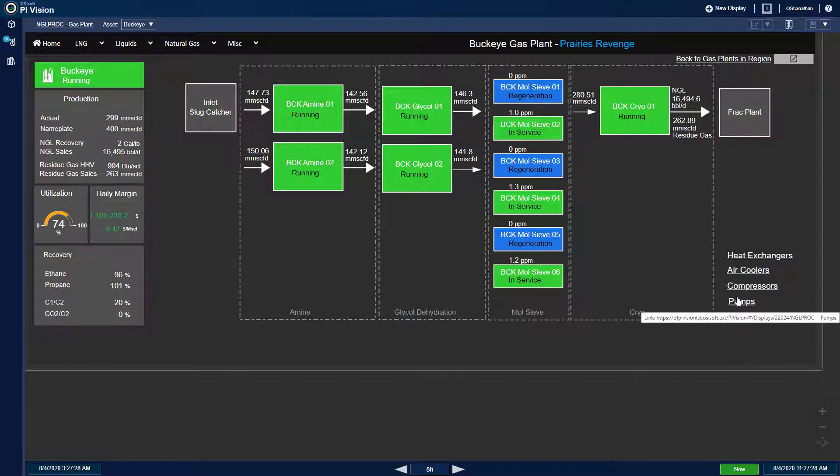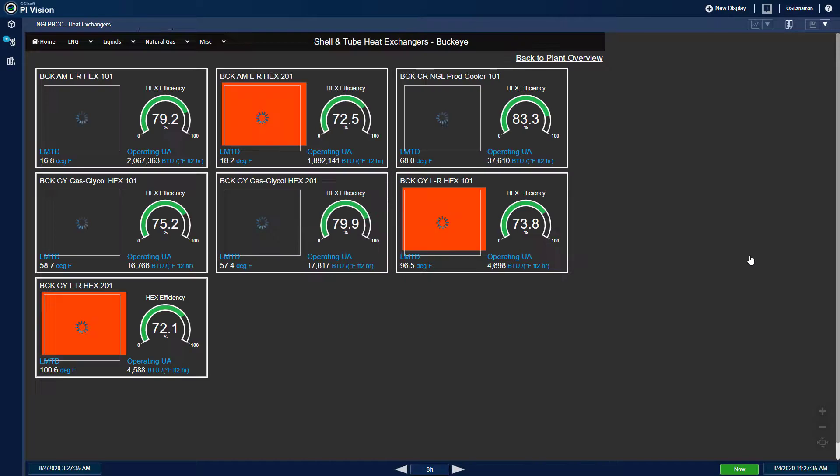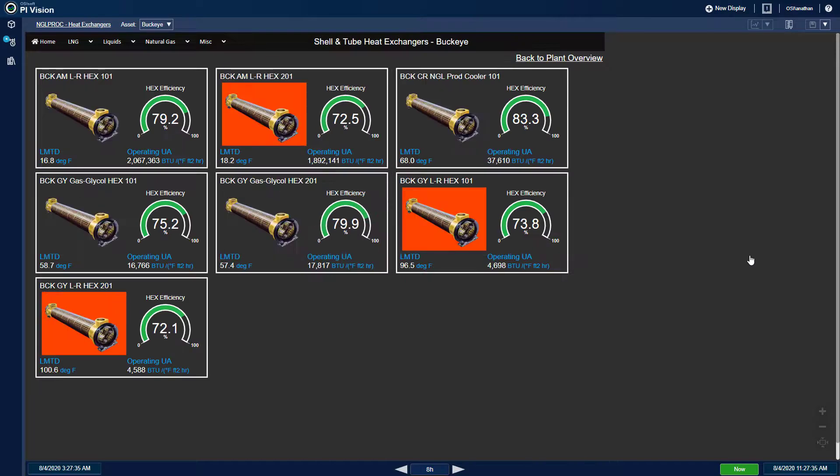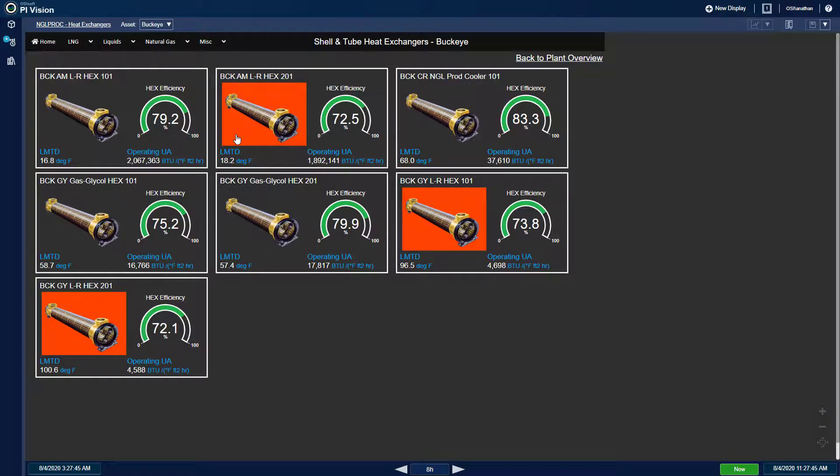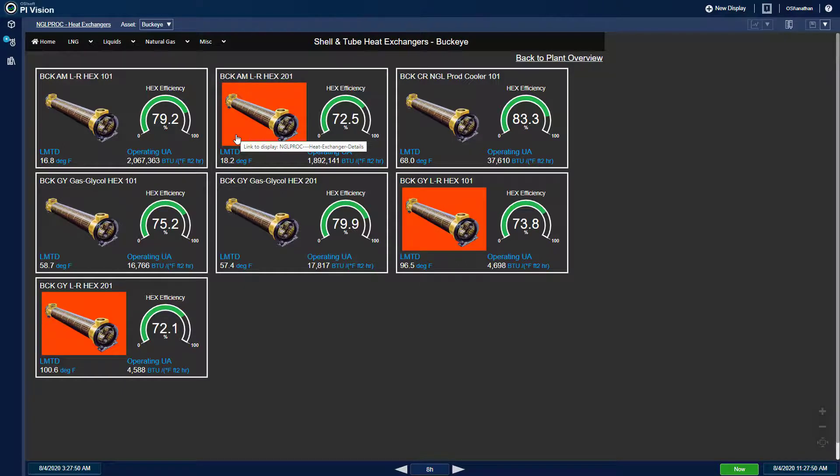On the heat exchangers page, I can view the current heat exchanger efficiencies, which is the ratio of operating UA to design UA. I can see a number of these exchangers are red and flashing, which indicates an efficiency less than 75%.